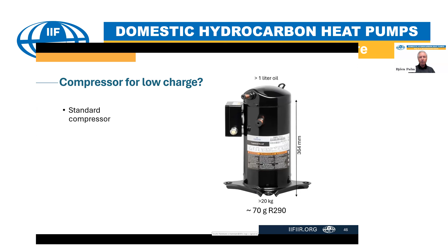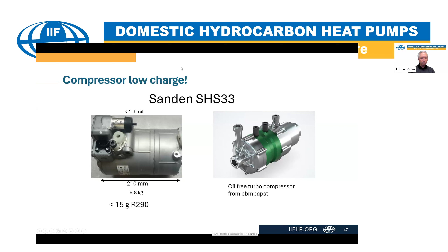But you could, of course, use some other type of compressor. And if we look to the left, this is a compressor of the type which is used in air conditioning systems in cars. And these are now being developed also for stationary applications. And you can see that in this case, it's less than 1 deciliter of oil instead of 1 liter. And the charge of refrigerant is 15 grams instead of 70 grams. And the weight is also a lot smaller. And just recently, there was a new type of oil-free turbo compressor presented onto the market. So there are developments ongoing now on components, specifically compressors, which can be used in future systems to reduce charge.